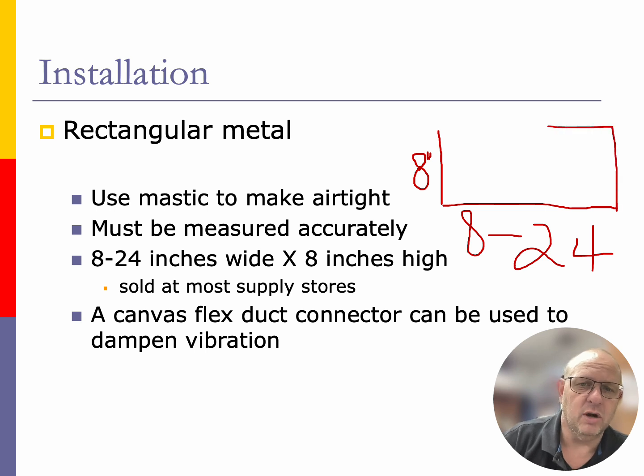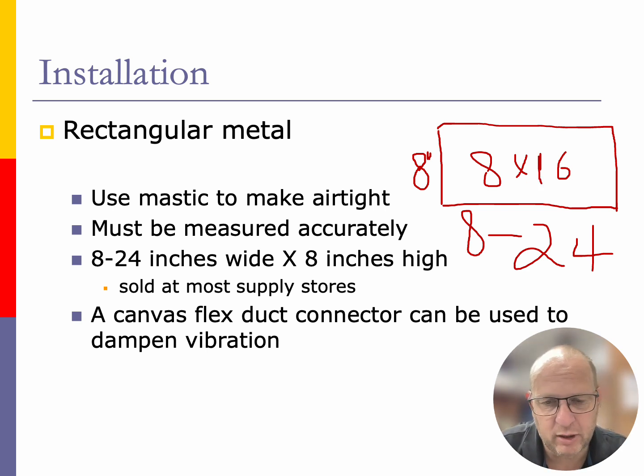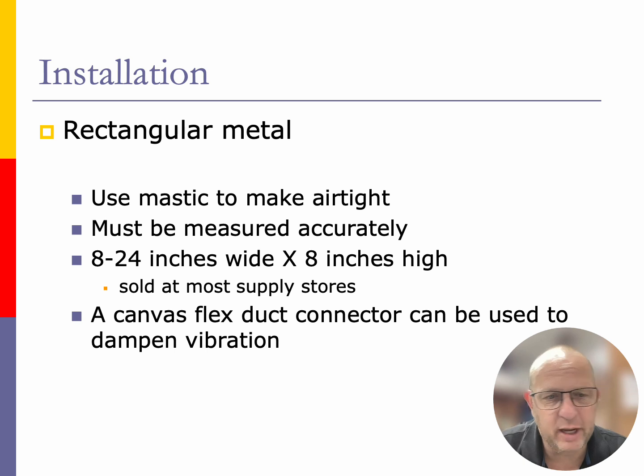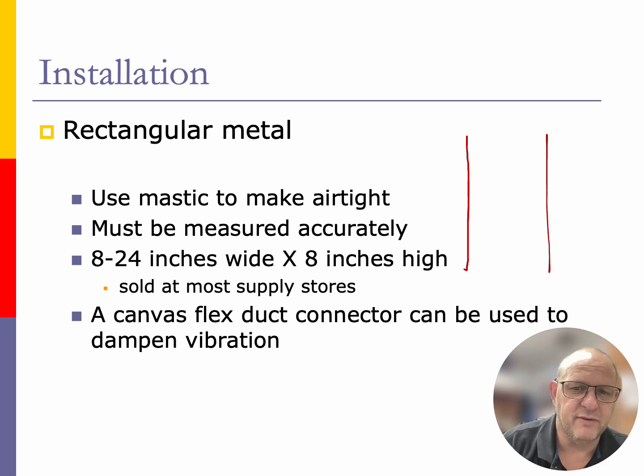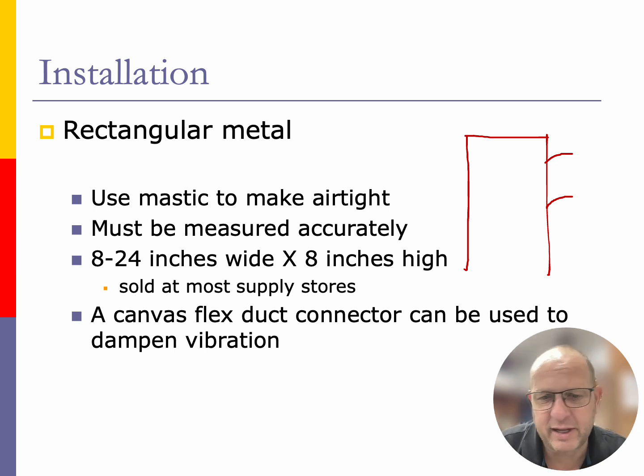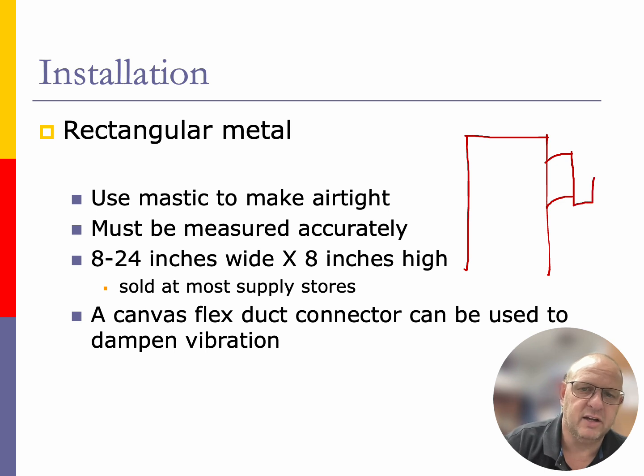So our square ductwork that's going to be sitting on there is going to be referred to as 8 inches by, and then we'll use the length, like 8 by 16 ductwork, as we're using it within our system to move that air along. Most of the ductwork is going to be sold at the supply store, so go ahead and pick that up there and look at it as we're going out there. Now, what we end up having is our furnaces are going to create some sort of vibration on our ductwork. And as we come off of our ductwork with a transition, which we'll discuss later on, to cut down on the vibrations of the actual furnace, we're going to put in a flexible connector between the takeoff and the actual square duct that's running in there.